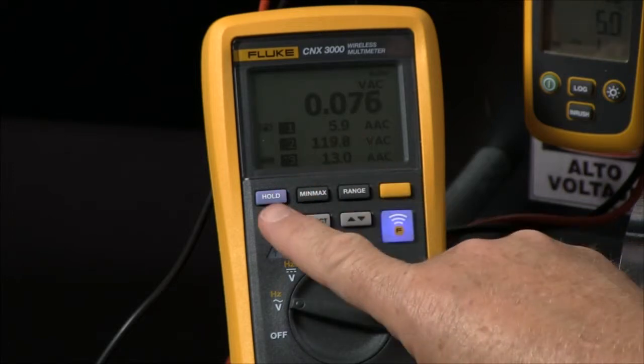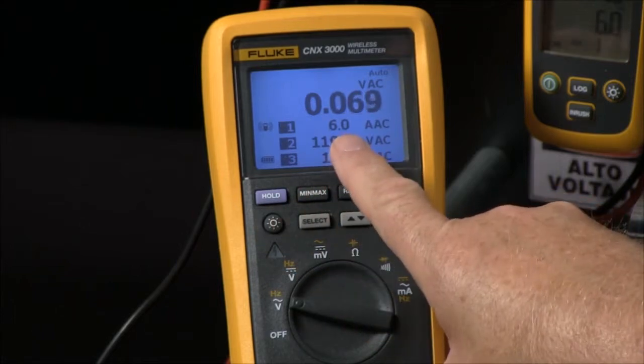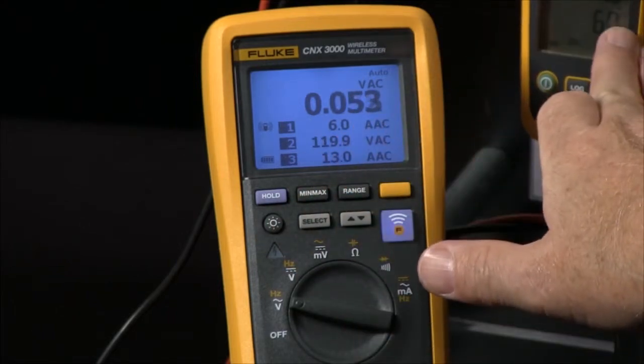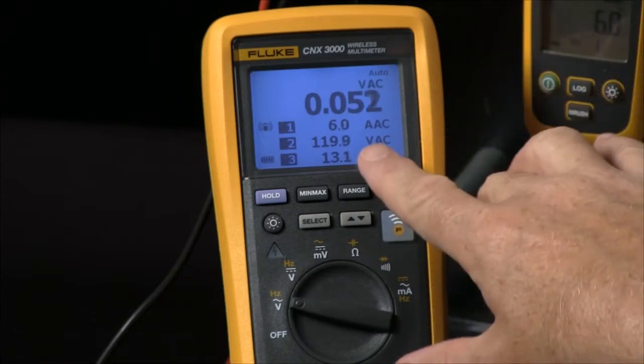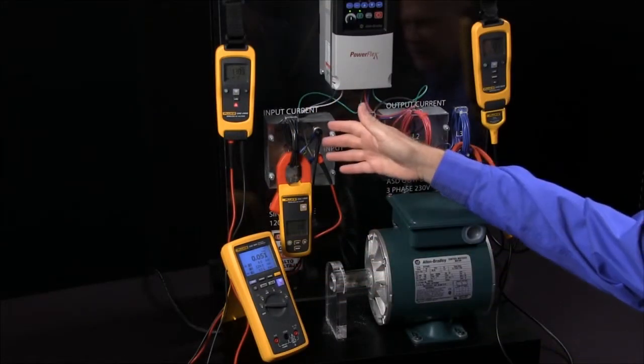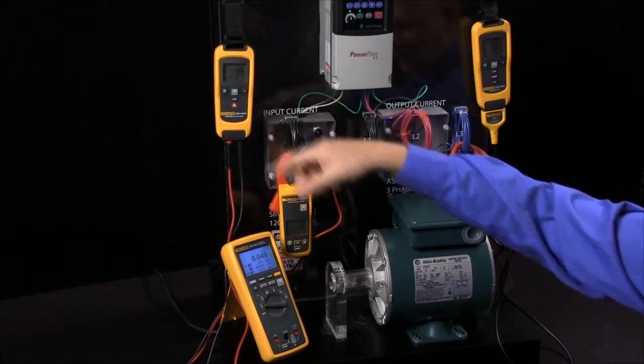So here we can see we have six amps that is coming in to the input of the drive. We have 119.9 volts that's been measured at the input going into the drive.